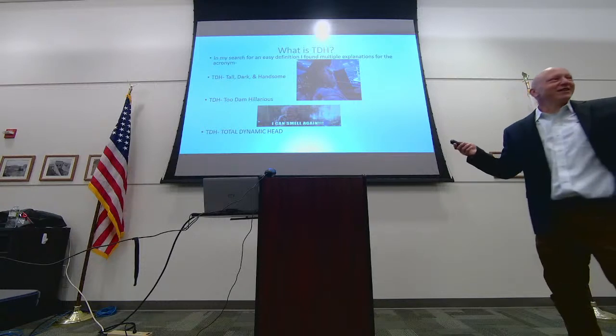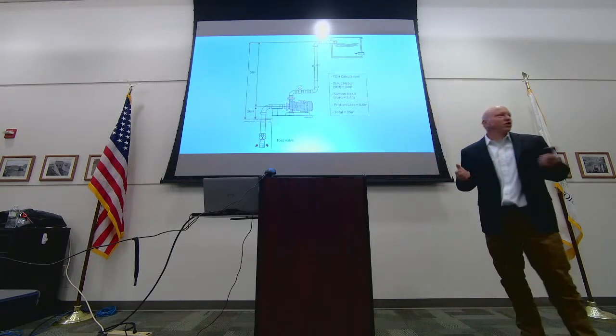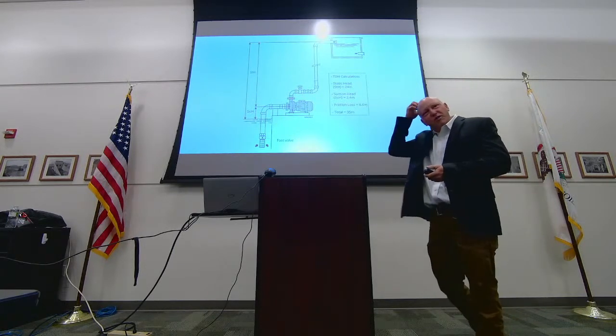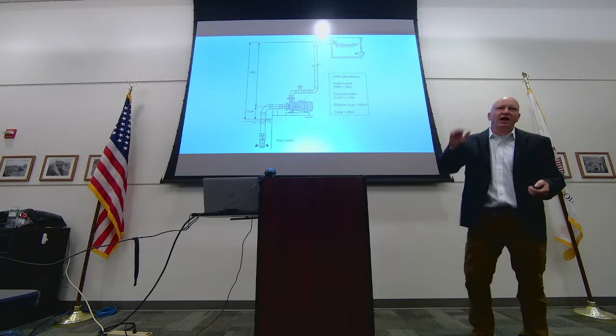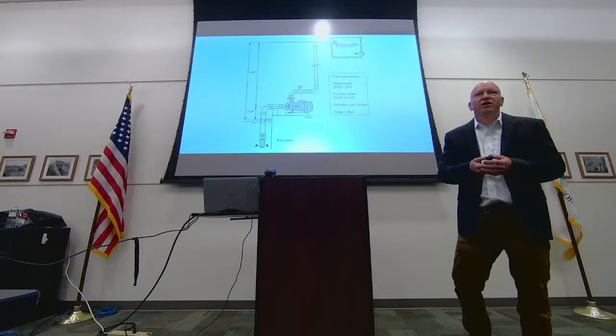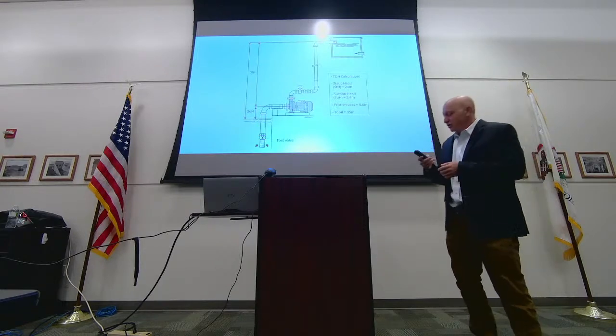You're not allowed to answer any more questions. So, TDH, static head plus suction head plus friction loss. Okay, so if you called me up and you said, John, I need 400 gallons a minute. I don't know what my TDH is, but I do know the elevation change is 32 feet. I know it's going in 4-inch old ductile iron. It's got 6 elbows, it's got a check valve, and it's got a gate valve. We can configure from that, easy for me to say, right, what your TDH is.